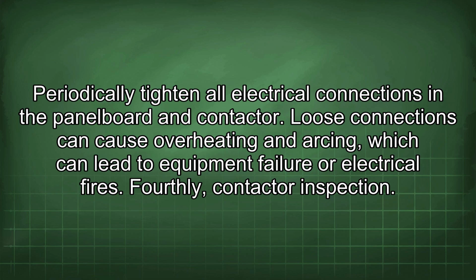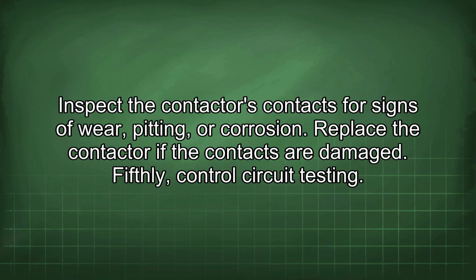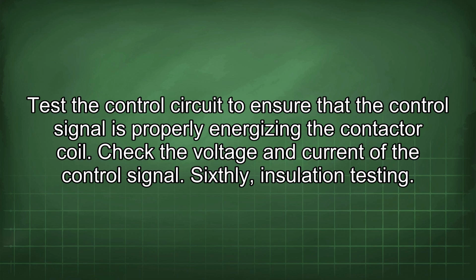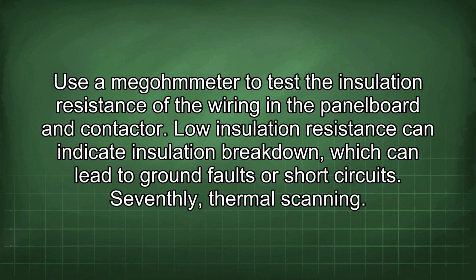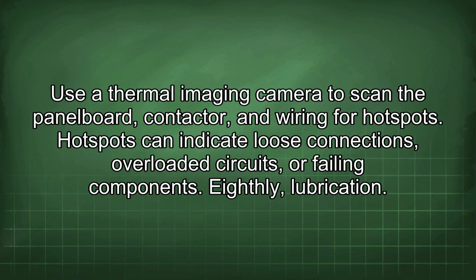Fourthly, contactor inspection. Inspect the contactor's contacts for signs of wear, pitting, or corrosion. Replace the contactor if the contacts are damaged. Fifthly, control circuit testing. Test the control circuit to ensure that the control signal is properly energizing the contactor coil. Check the voltage and current of the control signal. Sixthly, insulation testing. Use a megohmmeter to test the insulation resistance of the wiring in the panel board and contactor. Low insulation resistance can indicate insulation breakdown, which can lead to ground faults or short circuits. Seventhly, thermal scanning. Use a thermal imaging camera to scan the panel board, contactor, and wiring for hotspots. Hotspots can indicate loose connections, overloaded circuits, or failing components.